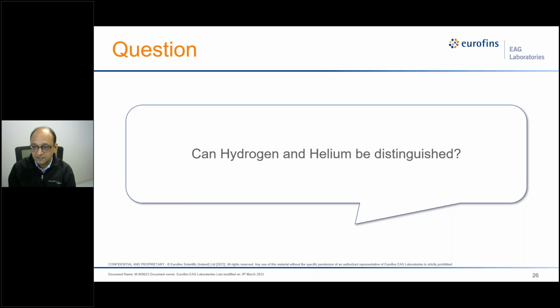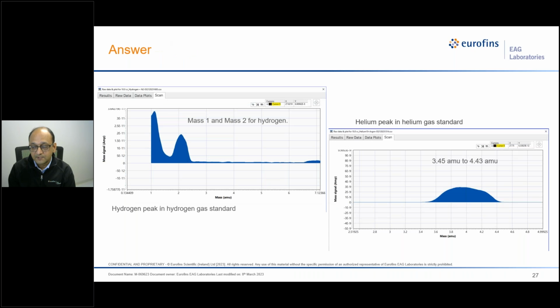Yes, and I think the simple answer is going through our scans. Here I put the scan for hydrogen calibration and the scan for helium. As you can see, hydrogen results in H+, which is mass 1, and mass 2, H2+. You can see these 2 peaks are due to hydrogen, and that ends almost at 3, somewhere in this region. And if you look at the helium peak, it starts from 3.45 to 4.43 AMU, centering around 3.95 or 3.98.